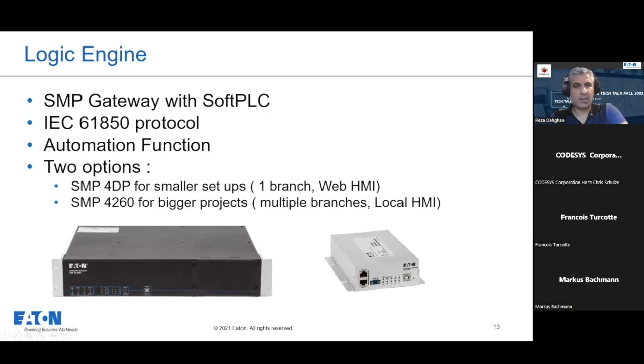System elements. For the logic engine, we use SMP Gateway. Francois already talked about different aspects of SMP Gateway. You know, there's a soft PLC engine running on SMP Gateway. The communication protocol was IEC 61850, basically to get especially the status points and fault status from the relays to SMP Gateway. We also used some of the automation function features in SMP Gateway.